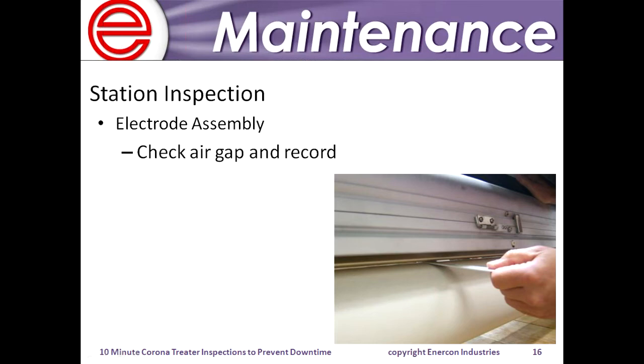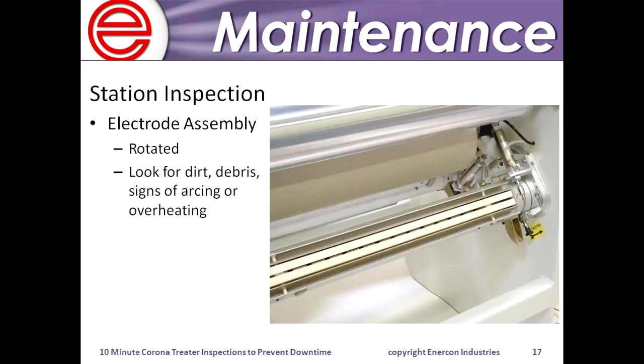So the first thing we want to do is check and record the air gap, because before we do any maintenance, we want to get a baseline, make sure we have it documented and recorded as far as what everything is set to before we begin work, just so we can return to that baseline if need be. This just shows when we first pivot the electrode assembly out of the treat position, take a look at the face of the electrodes, wipe them down with isopropyl alcohol.